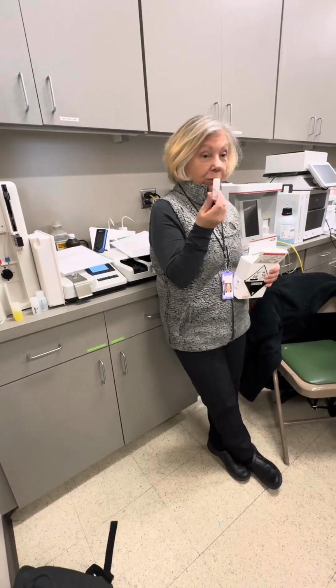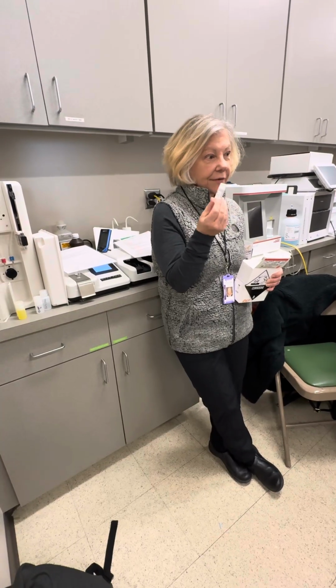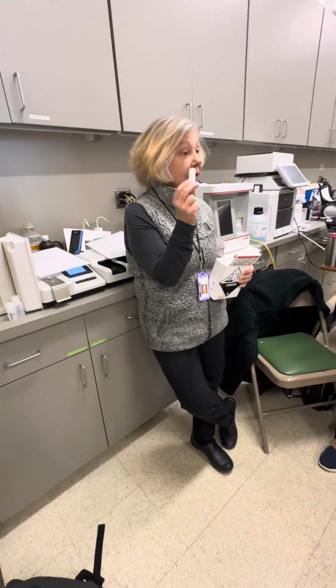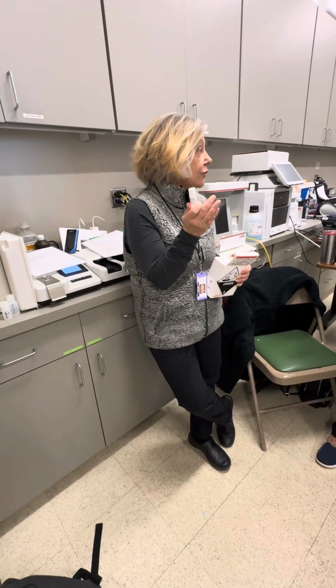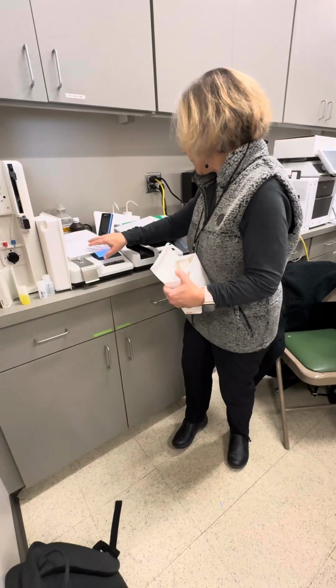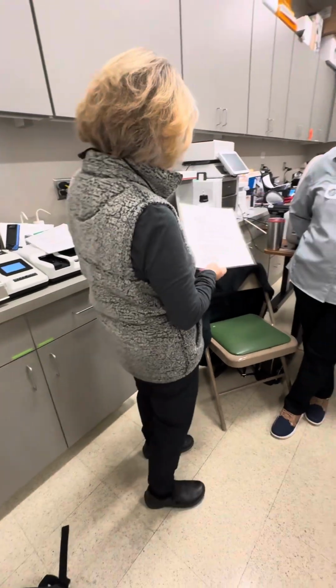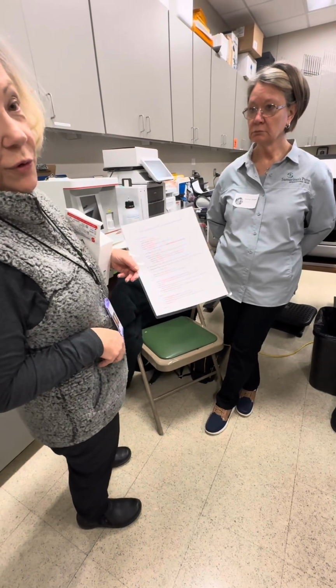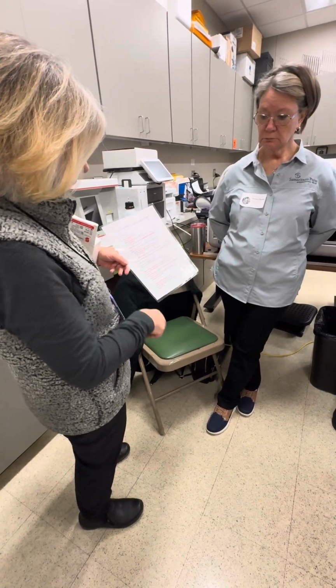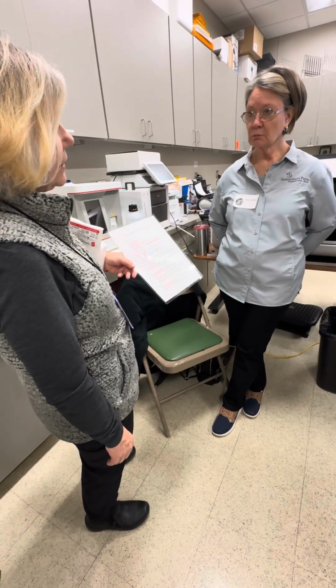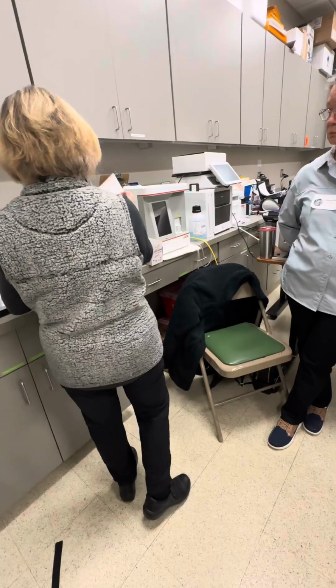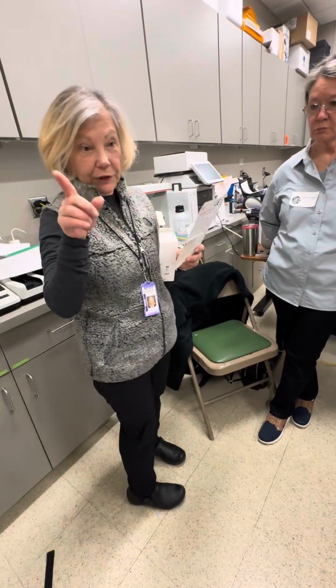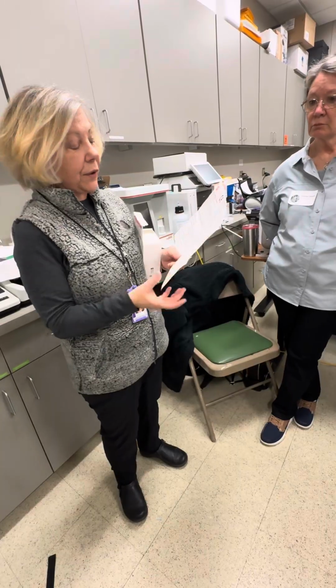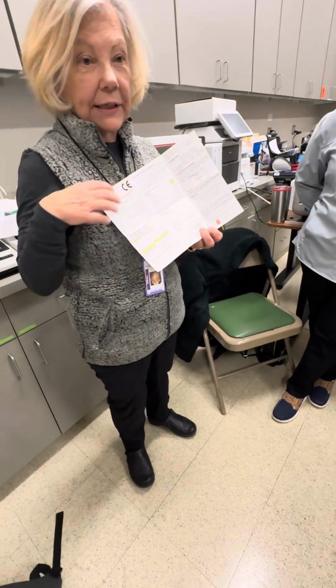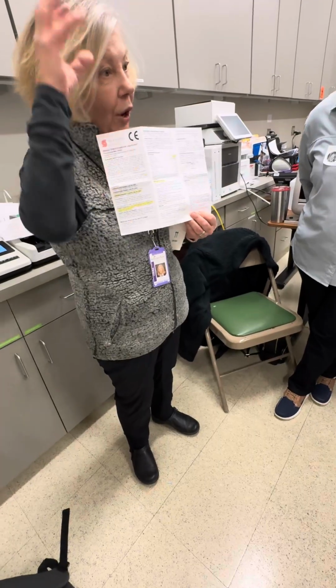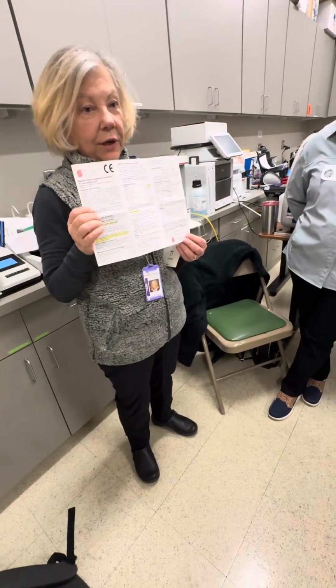Once in a while, it will tell you if it's lipids, one standard would work for all your lipids. But most of them come with their own standard. And there's a spot when you program it that says enter your standard. You can see that right on the back. It will walk you through, so this is why it would have taken your whole day. But we will walk you through this. We would do it together, how to program that test. And the package insert actually tells you which filter, or which wavelength, to read it through. So all of that is with the manual testing, which will tell you which filter, and you would program it according to the package insert.